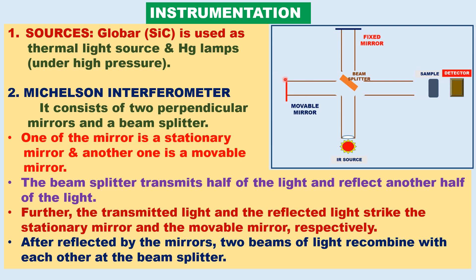One mirror is fixed and another is a movable mirror. The beam splitter splits the IR beam into two halves — one half is transmitted and another half is reflected to the movable mirror. The transmitted light from the movable mirror and fixed mirror meet at the beam splitter to recombine. There are two possibilities: constructive interference and destructive interference. The beam is then allowed to pass through the sample and then the detector.